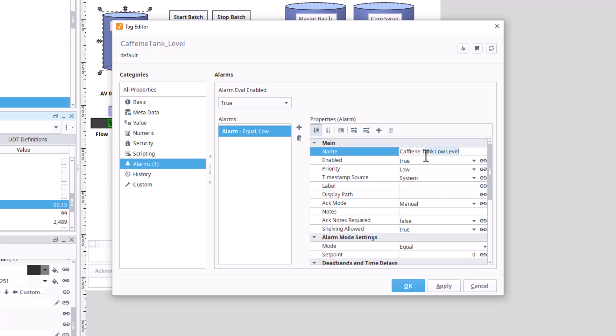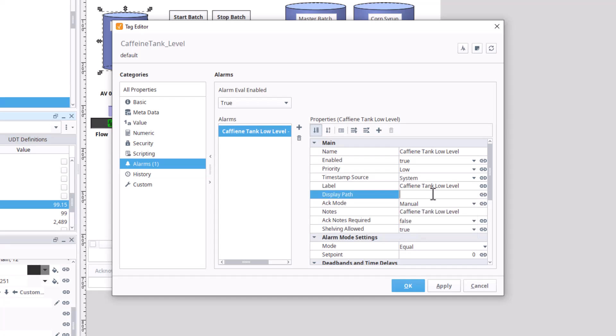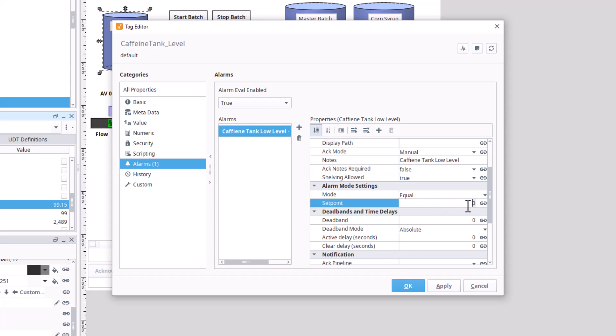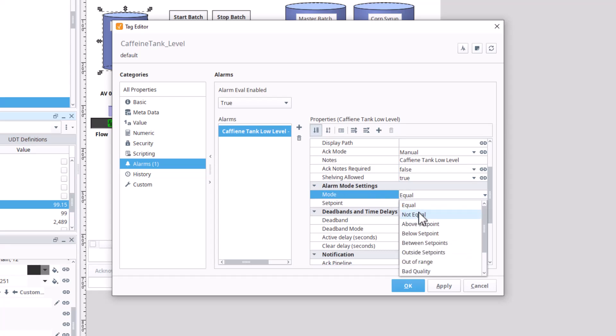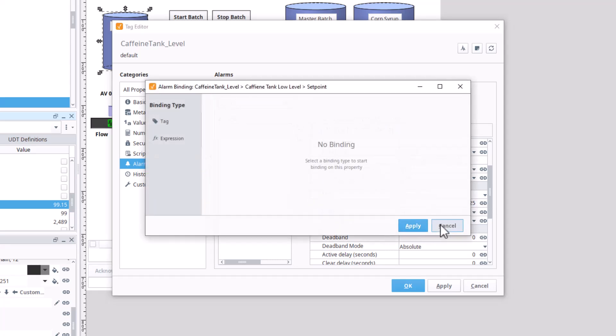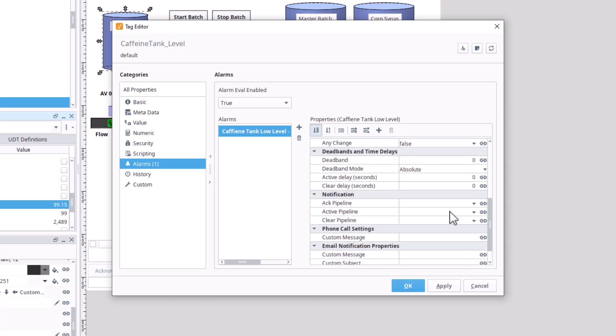I'll put that same name into my notes field, and also give it a label — the label is for HMI graphical purposes. For the alarm mode, I want the alarm to trigger when the value is below a setpoint. The setpoint can be manually entered or bound to a tag; in this case I'll hard-code it to 25.